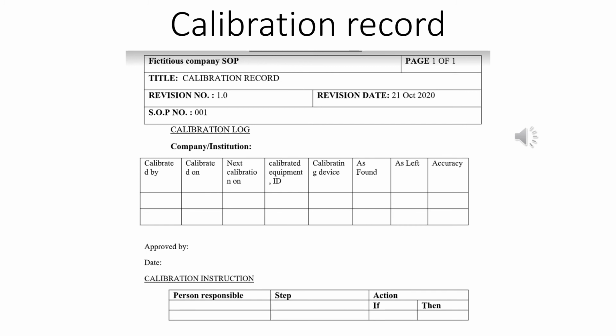Write down the name, the make, the model, how long it has been used, and as found, what the data was, as left, what the data was, and whether it is adjusted to the accuracy, with the criticality of the data maintained. And who approved it after the calibration, normally the supervisor or the technician or the head technician, and when, and what kind of problem was found during the calibration, and if a problem is found, what step is taken, and whether the problem was solved. This is really important to be written down.